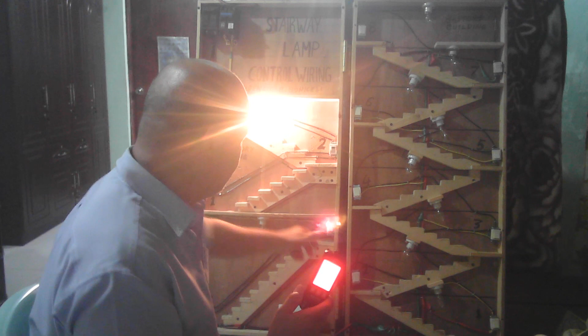No more power supply, but you still have lights. No more power supply on the convenience outlet, but you still have lights. Why? Because the breakers are separate. The circuit breaker for the convenience outlet and the circuit breaker for the lights are different, and that is the standard now. You must not put the lightings and the convenience outlet into one circuit breaker.